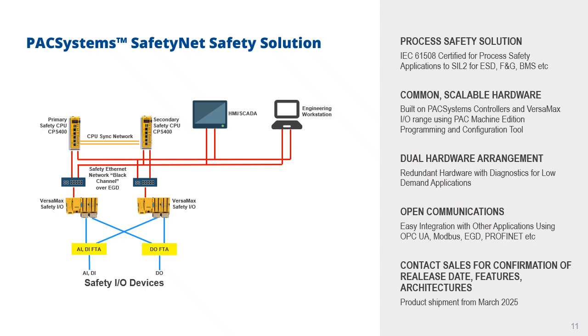So you would have a HMI SCADA system, but that would be used for monitoring and diagnostics and fault detection, not for actually controlling the system and performing set points. Even something like the shutdown, that would very rarely be software defined. Normally you would do that in hardware to make sure that you've got control over the safety functions. And the reason for that is, it's pretty much impossible to certify for safety a Windows-based system. There's too much that can go wrong, so you can't prove that the system will be safe. So that's why you normally use the HMI SCADA for monitoring only.